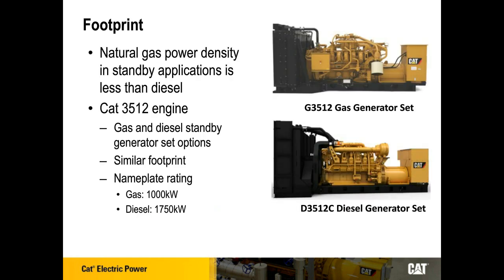Another thing that comes up when comparing natural gas and diesel generator sets is footprint, meaning the size of the generator set and what size footprint it fits into in your facility. In general, the power density of natural gas generator sets is much less than diesel. So what does that mean?